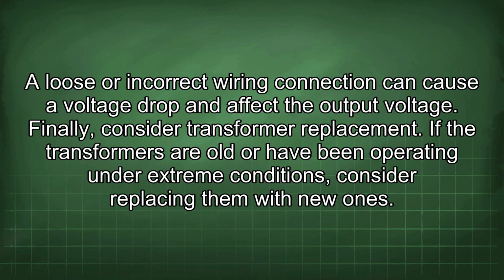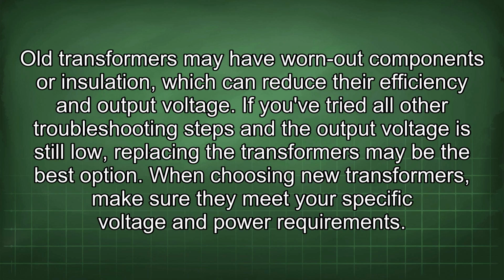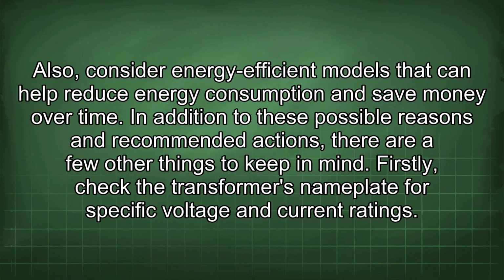Finally, consider transformer replacement. If the transformers are old or have been operating under extreme conditions, consider replacing them with new ones. Old transformers may have worn-out components or insulation, which can reduce their efficiency and output voltage. If you've tried all other troubleshooting steps and the output voltage is still low, replacing the transformers may be the best option. When choosing new transformers, make sure they meet your specific voltage and power requirements. Also, consider energy-efficient models that can help reduce energy consumption and save money over time.